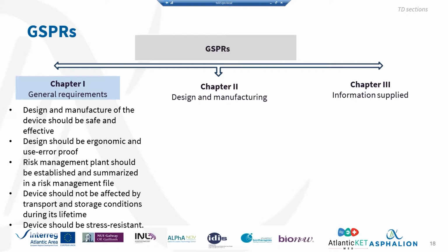That means your device has to be stable. You will have to perform stability studies to demonstrate that your device complies with this requirement. And then you've got that the device should be stress resistant, as we were saying, stability testing. Okay, as I was saying, these general requirements are applicable to all the devices. Obviously, there are particularities depending on your device, but this Chapter 1 is like the most general.